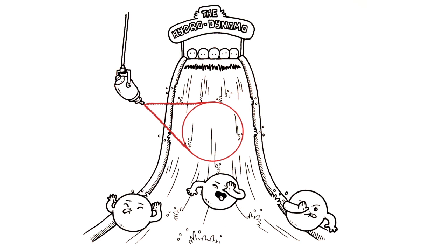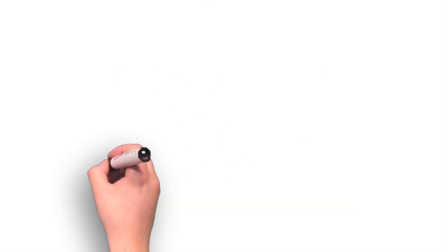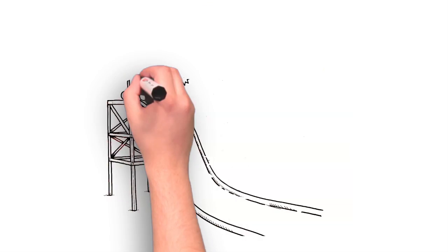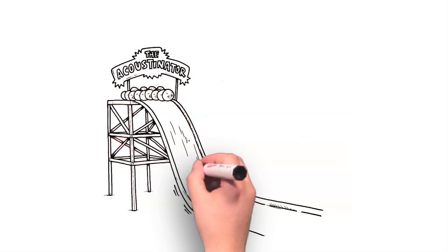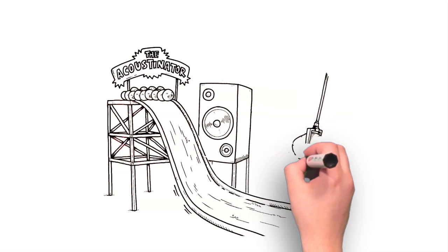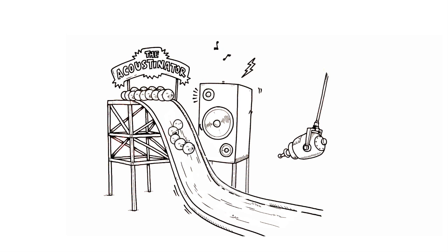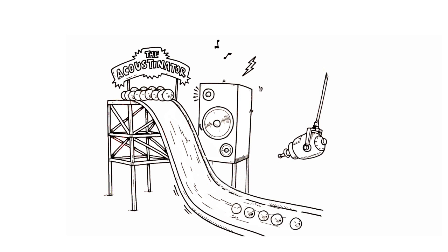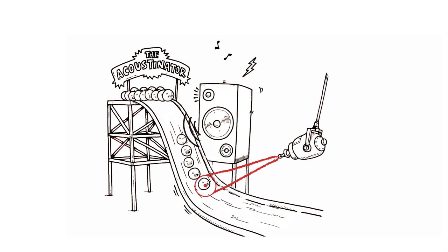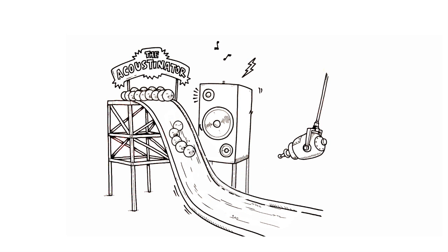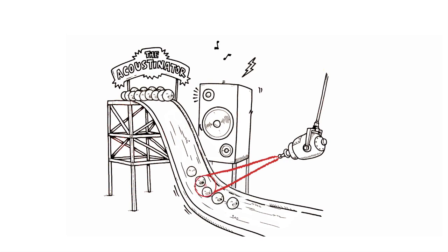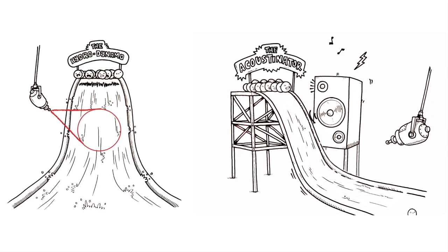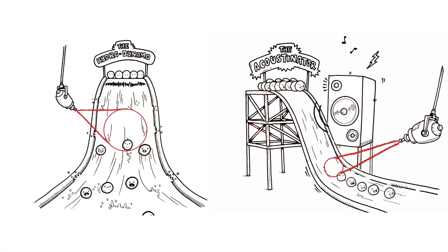It was time to innovate. The difference with acoustic focusing is that to a great extent, focusing is decoupled from the lateral movement of cells. In this way, particles or cells are focused in the acoustic device prior to entering into the manifold, where they're met with sheath fluid. With acoustic focusing, sample rates can be increased by over 10 times compared to hydrodynamic focusing instruments while still maintaining focus.